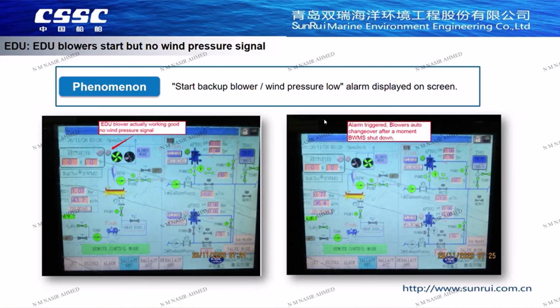Next is the wind pressure switch cannot detect the wind pressure. The actual phenomenon can refer to the below two photos. One is confirmed that EDU blower operates normally, but there is no wind pressure signal in this place. After time delay reaches, the EDU blower fault alarm will be triggered and the standby blower will start automatically. If there is still no wind pressure signal after the standby blower starting, the system will trigger shutdown alarm.